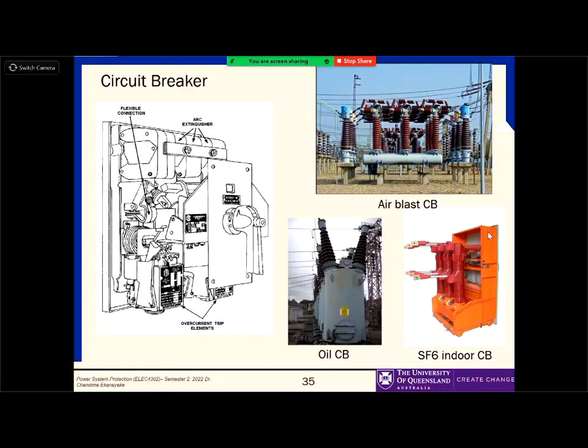Indoor substations are mostly with SF6, sulfur hexafluoride, which is a gas and a very good insulating gas. So you can have circuit breakers within a building environment. Usually substations are outside, but SF6 substations can be mounted inside a building, so the size is smaller, safety is higher, and there are a lot of other advantages as well.